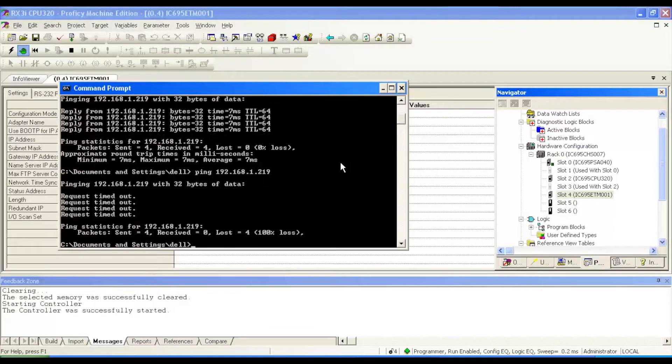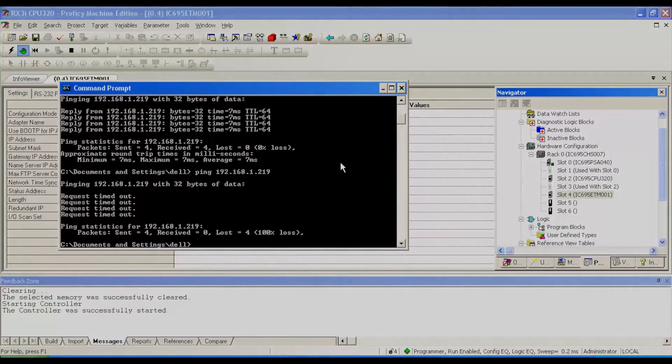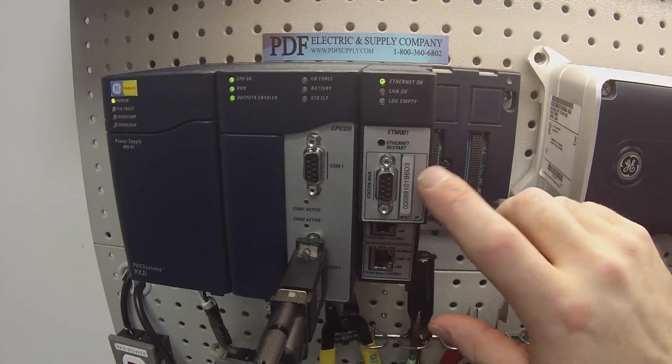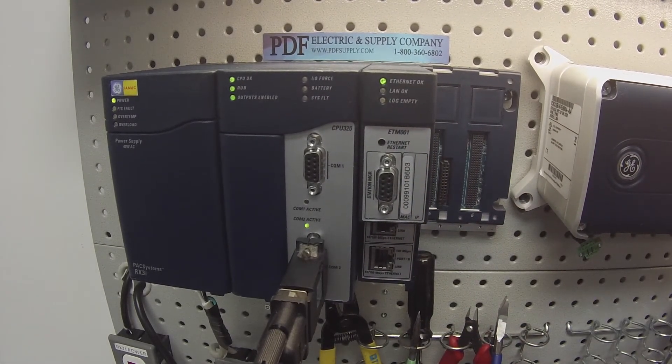What I do every time I test an ethernet module is I unplug all my ports, I use the same address, I ping it, and if I get a reply, that means that I know for sure I've only been testing this particular module and nothing else.